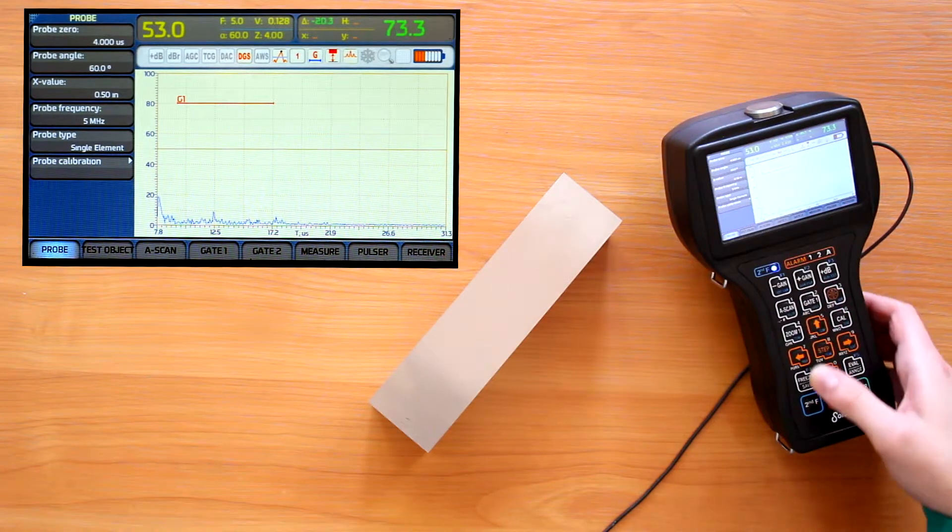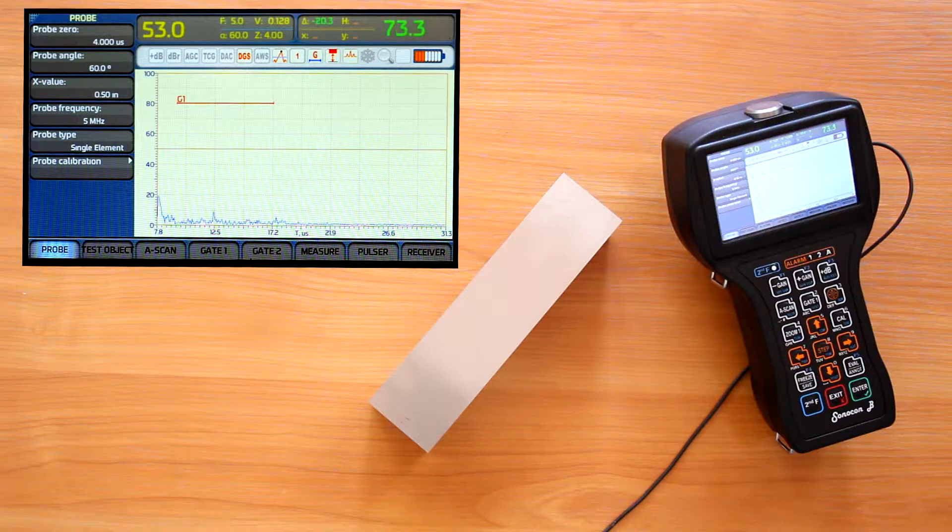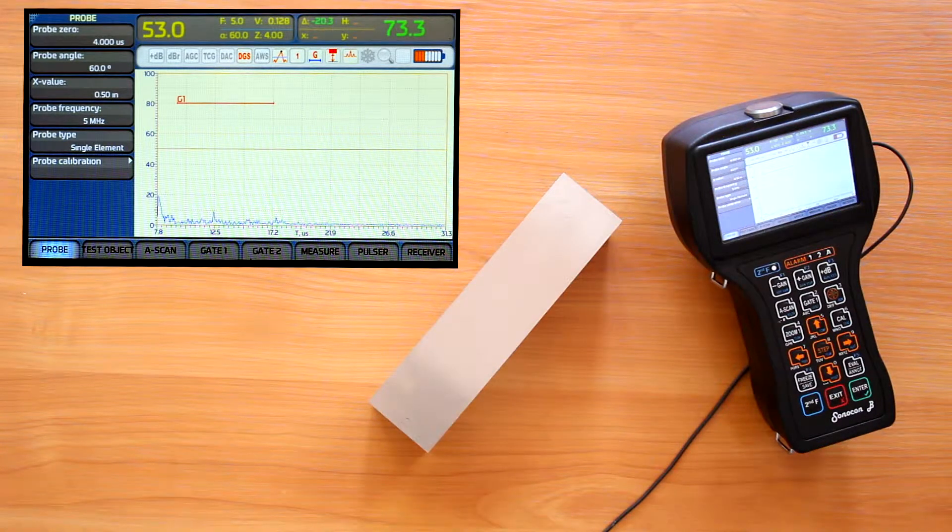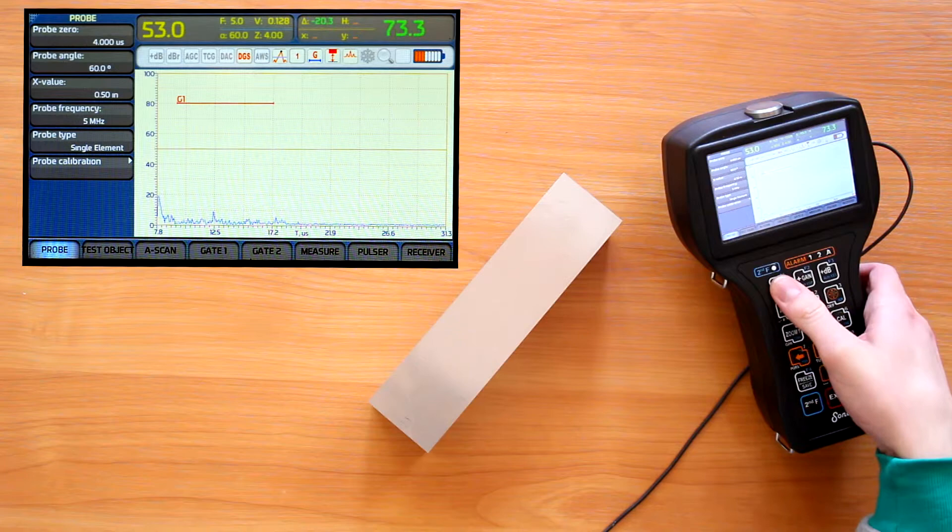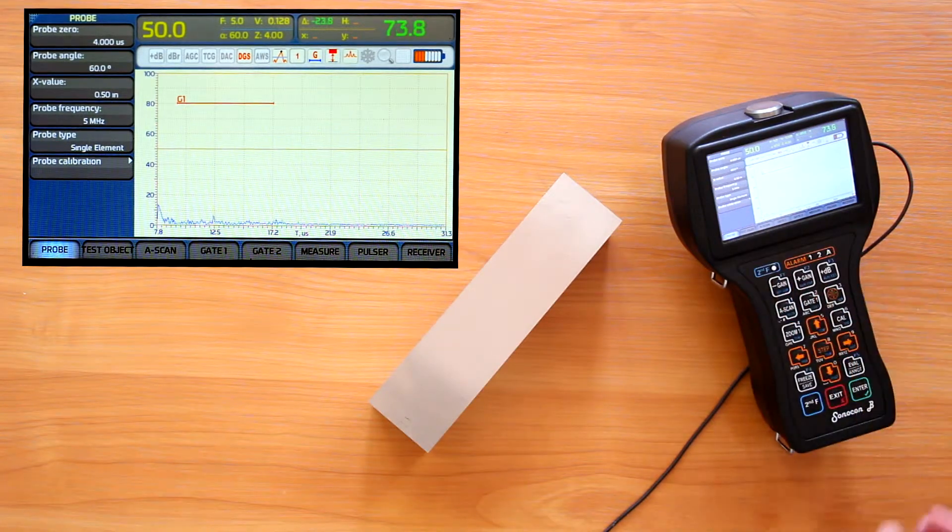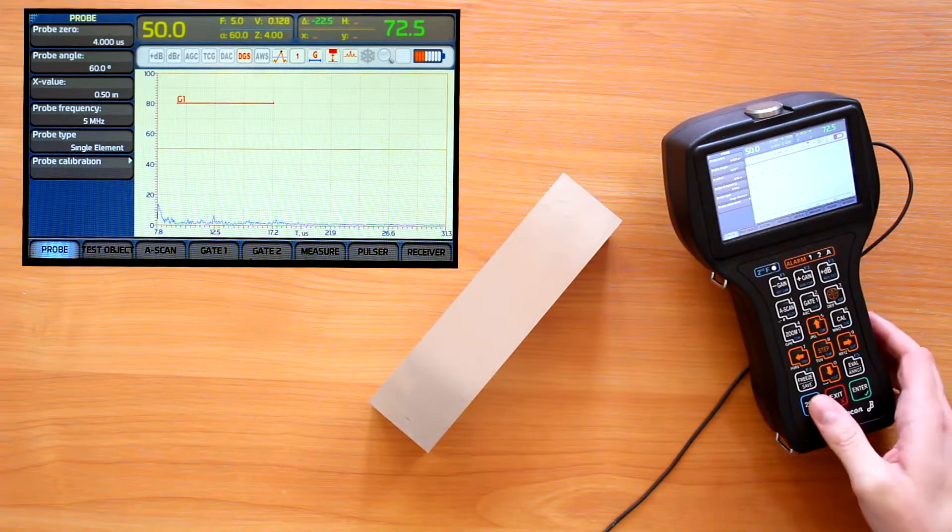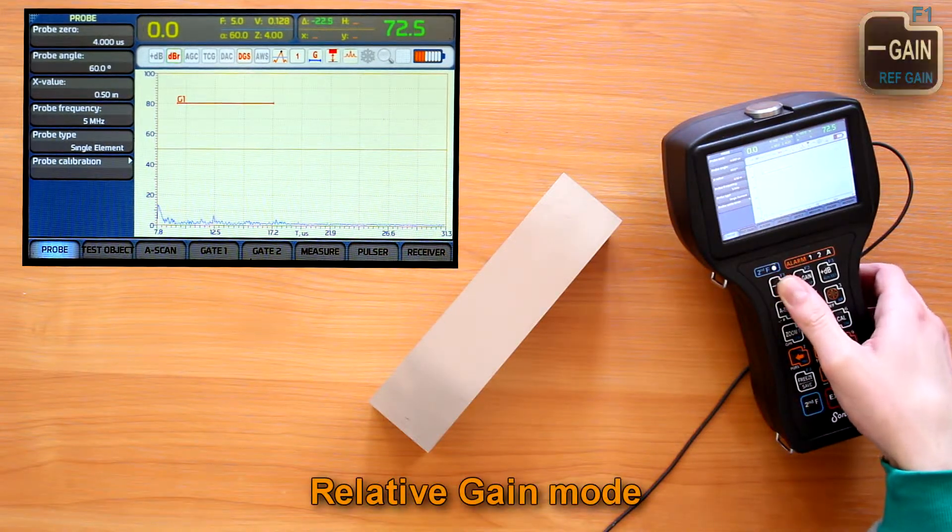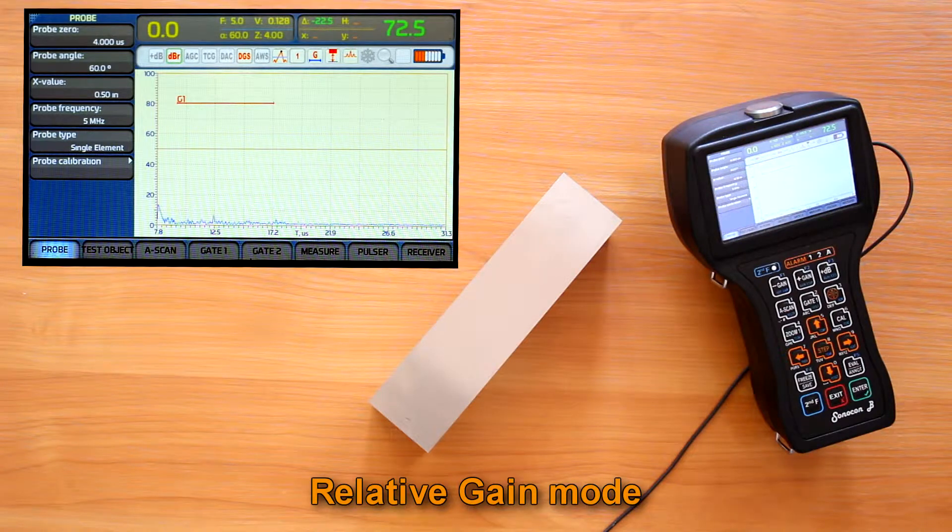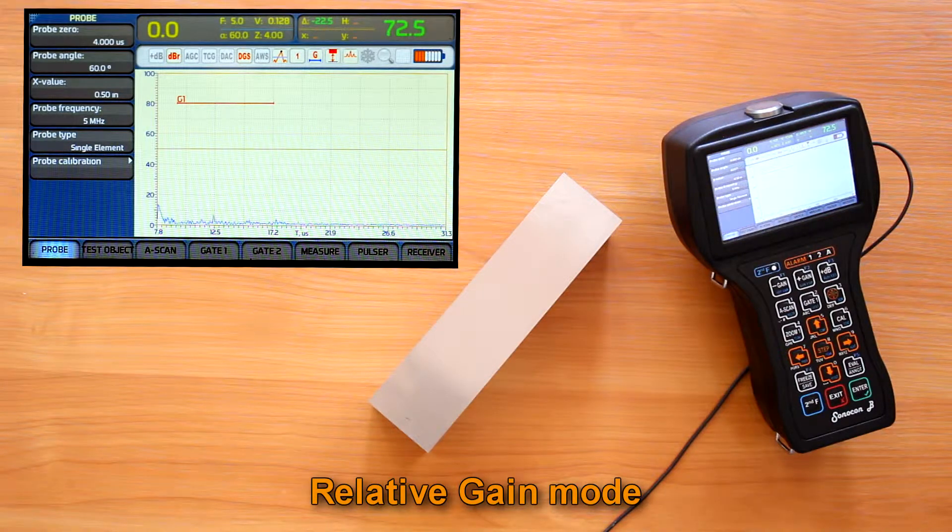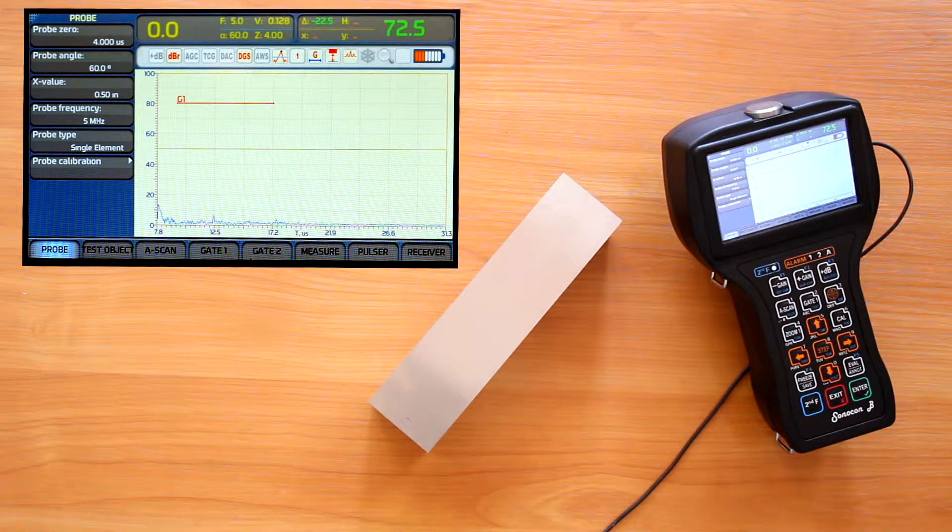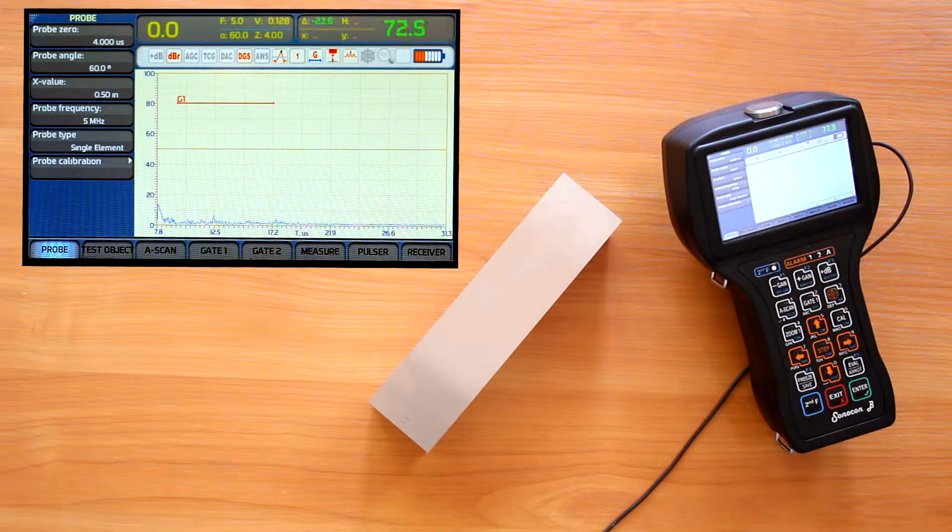Another option used in some testing techniques is so-called relative gain. In this mode we set the gain to some reference value, let it be 50 decibels in our case. And activate the relative gain mode with second function plus gain minus. The displayed gain value changed to 0 and DBR indicator goes on indicating this is not absolute gain, but relative to the reference one.